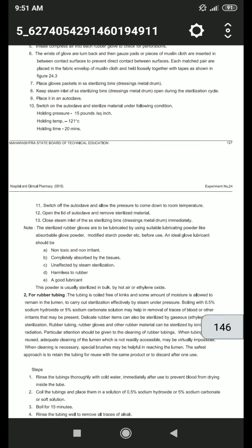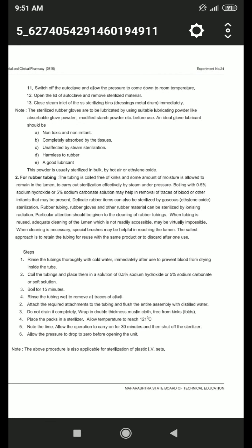Okay, now the second item, rubber tubing. The rubber tubing is coiled free of kinks, and some amount of moisture is allowed to remain in the lumen to carry out the sterilization effectively by steam under pressure. Boiling with 0.5% sodium hydroxide or 5% sodium carbonate solution may help in the removal of traces of blood or other irritants that may be present. Delicate rubber items can also be sterilized by the gas ethylene oxide. Rubber tubing, rubber gloves and other rubber materials can also be sterilized by ionizing radiation.